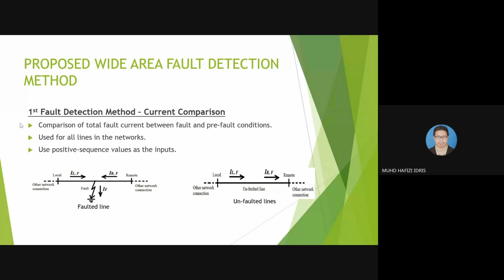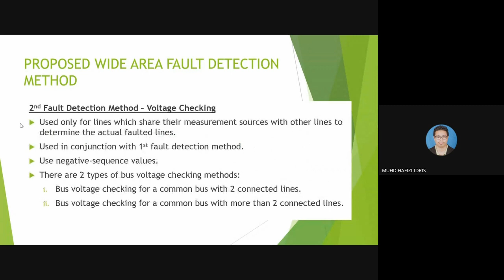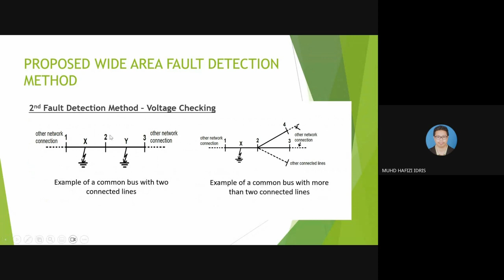And this is the second fault detection method, which uses the voltage checking method. This method is only used for the lines which share the measurement source with other lines. It must be used in conjunction with the first detection method, and it uses the negative sequence values as the inputs. There are two types of voltage checking method. The first one is for the common bus which has two connected lines, and the second is for the common bus which has more than two connected lines.